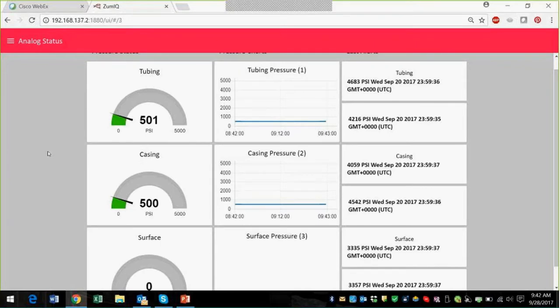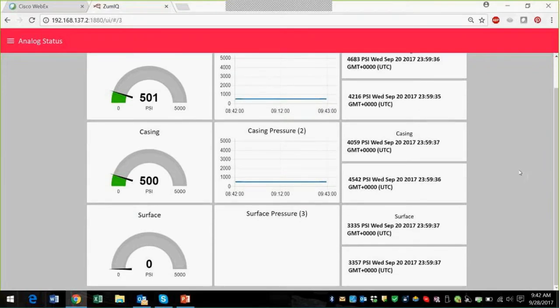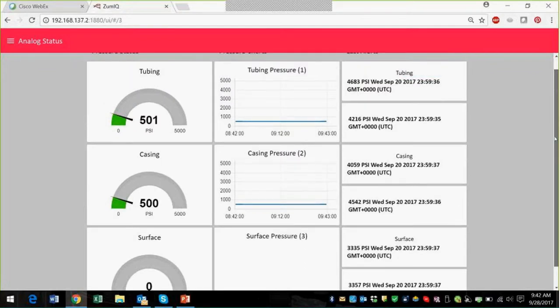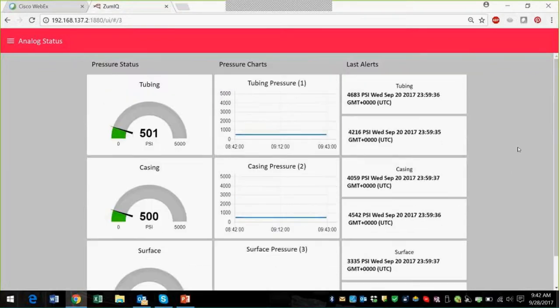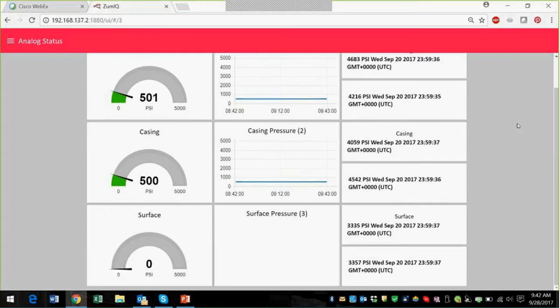This is the pressure status. In this simulation, we're modeling tubing, casing, and surface pressure. It looks as if the surface pressure is offline — it was taken off a couple of days ago. But you can see this would appear on your dashboard and you'd know almost immediately. In this case, you could send someone out to put the pressure sensor online again, and you would get an alert if that's the way you set the system up.